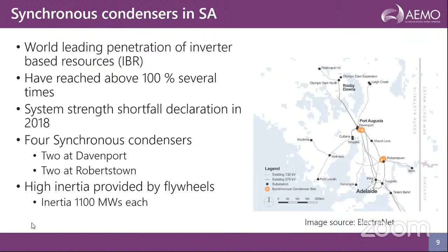In 2018, we declared a system strength shortfall in South Australia, which resulted in the transmission network service provider, TNSP, going and procuring system strength services, and they decided to install 4 synchronous condensers in South Australia. 2 at Davenport, which is shown on the figure, the top part of the middle of the figure, and 2 at Robertstown. So there are 4 synchronous condensers which are now in commercial operation in South Australia, which has resulted in filling the system strength shortfall which was declared in 2018. Now, these synchronous condensers are a little bit different from traditional ones. These are high inertia synchronous condensers. They have a flywheel, and each synchronous condenser has 1100 megawatt seconds of inertia, which is provided by the flywheel.